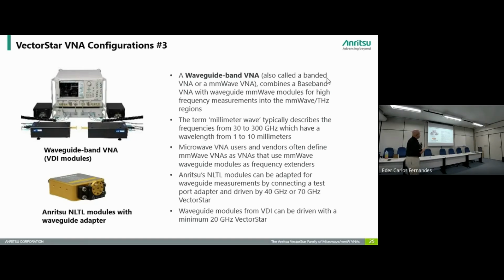The VDI modules use an external power supply. The picture here is not totally up to date. The newer style of VDI modules are actually more compact. They're a little bit smaller than what you see here. And the power supply is also more like an AC adapter, like we use with the AutoCal or the OE module, a smaller standard AC adapter rather than this specialized power supply. But again, it's an external power supply because these modules require a little bit more power than what we're able to deliver out of the standard test set here. But again, we can drive this with a 70 gigahertz mainframe VNA or even lower frequency if all that's desired is a banded system. But if it's broadband, it's got to be one of these modules here to begin with.